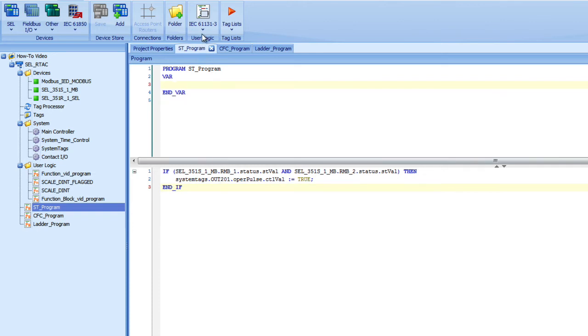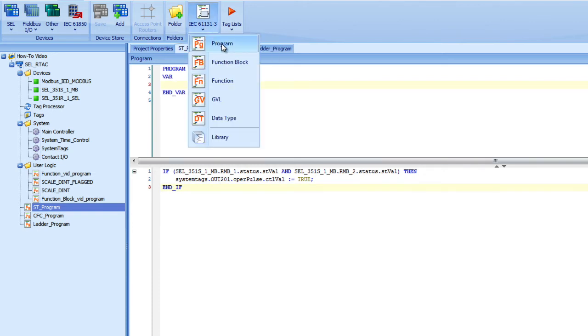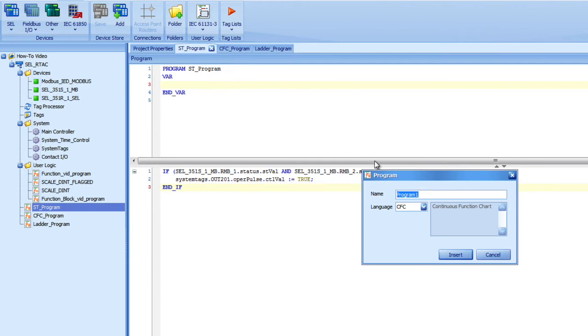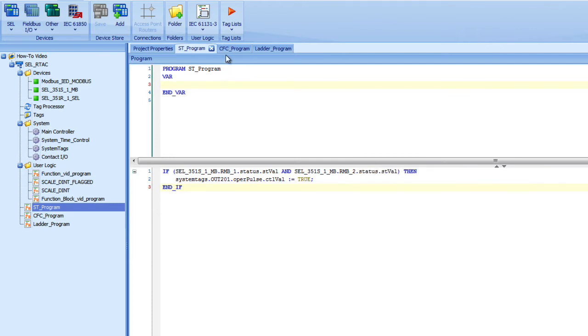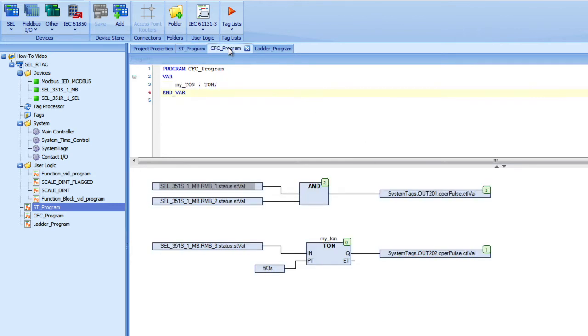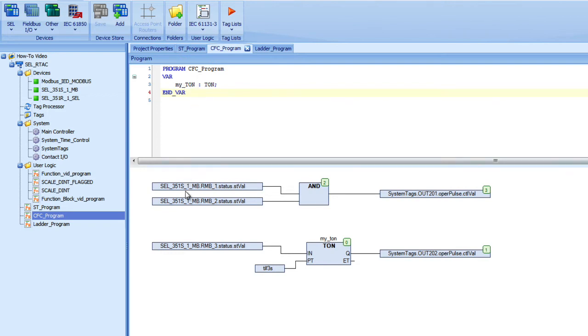Let's do the same thing with continuous function chart. So again I go to the 61131, select new program, call it continuous function chart. Same thing at the top, you have the variable area. And I'm doing something a little bit different here that I'm going to explain in just a second. So the first couple blocks here show that I have two inputs. I'm anding them together. And the output of that and function will set an output in the RTAC, just like I did before.